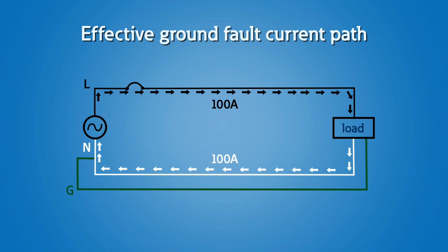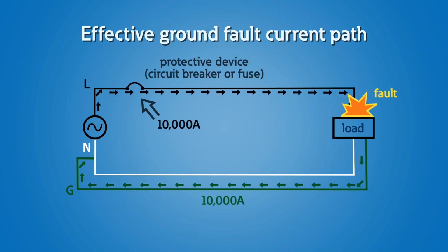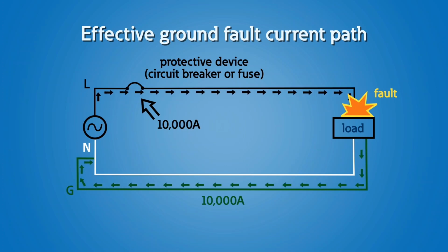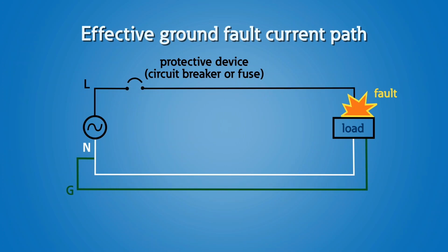Why are we talking about this? Why do we worry about grounding and bonding? We want to establish an effective ground fault path, and we also want to think about touch potentials or step potentials, for two different reasons. First, the effective ground fault current path: we're intentionally constructing a low impedance conductive path that's designed to carry the fault current from the point where the ground fault occurs in the system back to the source. The reason we do that is we want to make sure that we open the overcurrent protective devices, which could be equipped with ground fault protection of equipment or GFCI protection. We want to make sure that we open those and give enough current for those to detect that fault.